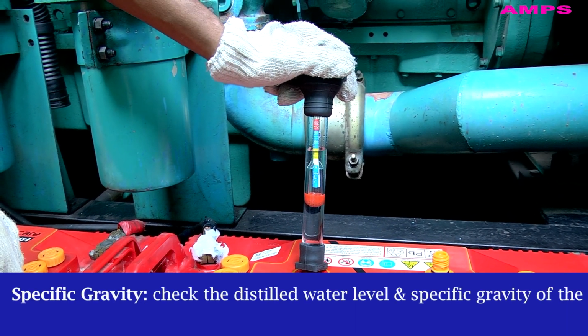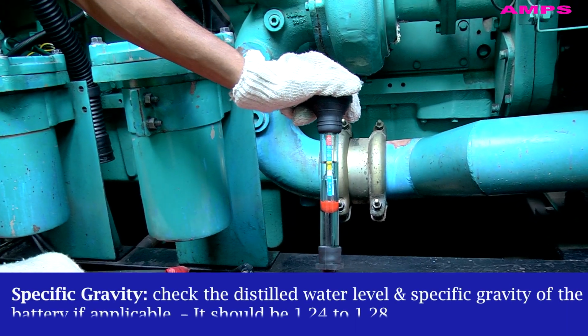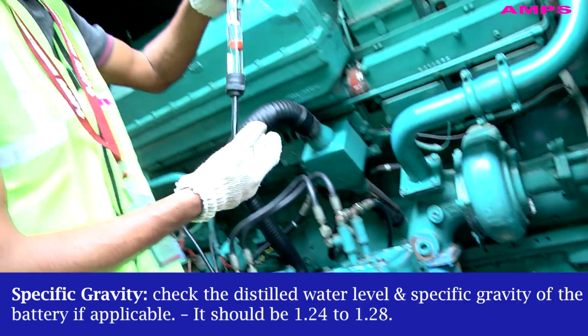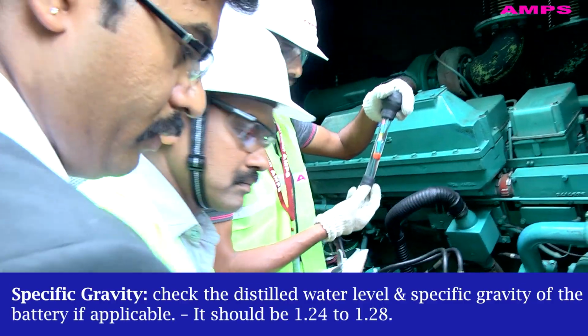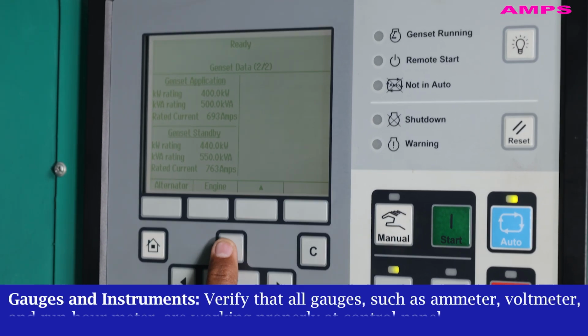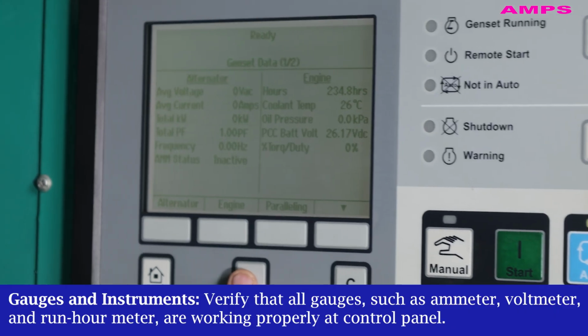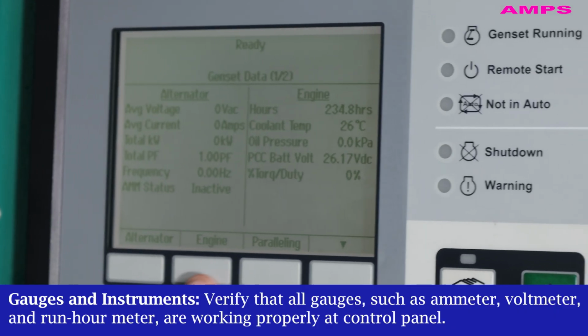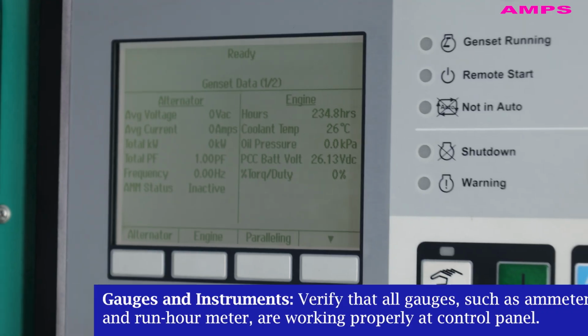Specific gravity: check the distilled water level and specific gravity of the battery if applicable. It should be 1.24 to 1.28. Gauges and instruments: verify that all gauges, such as ammeter, voltmeter, and run-hour meter, are working properly at the control panel.